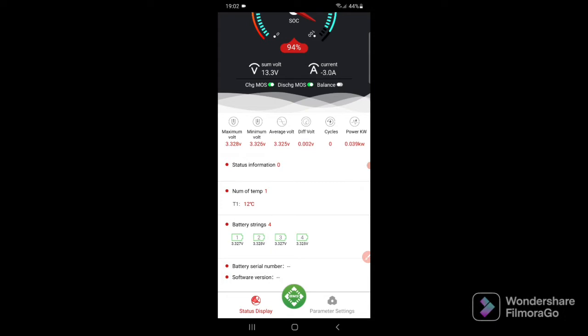Obviously what you want to try and do is get these as close as possible. You've got your average voltage at 3.325, and we've got, as it fluctuates, a differential voltage of 0.002. That means there is 0.002 volts difference between the cells, cumulative. Ideally you want that at 0, but obviously you've got to charge them, and then you get into the balancing stage.